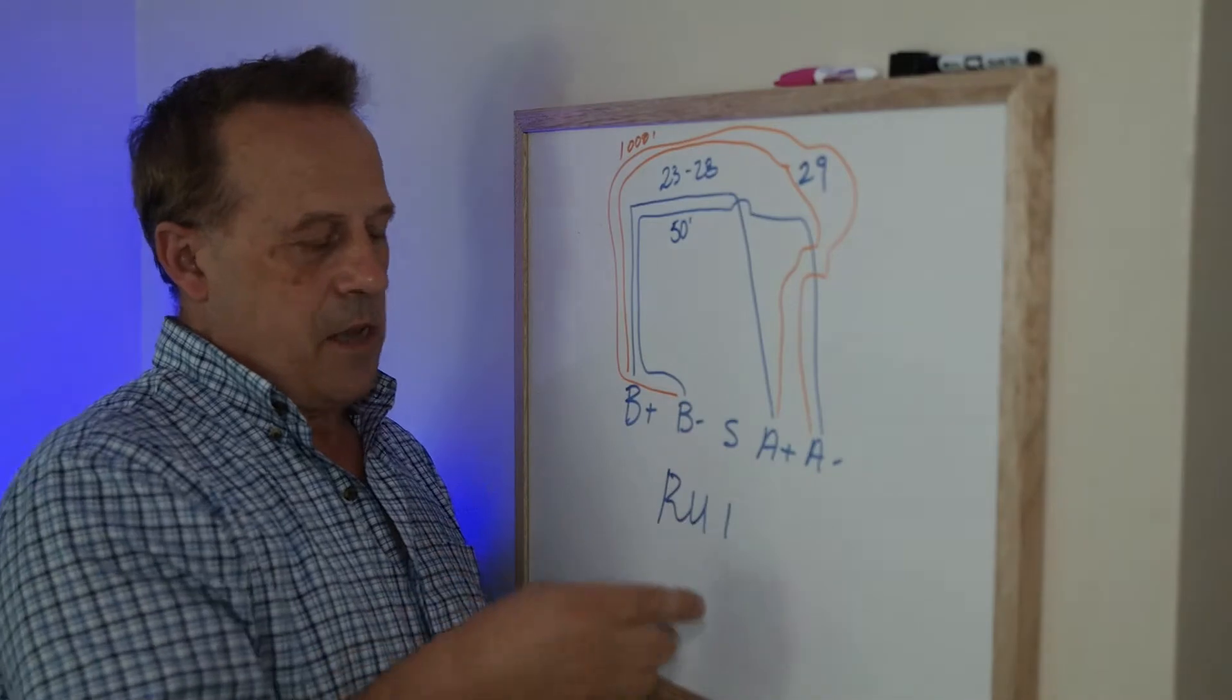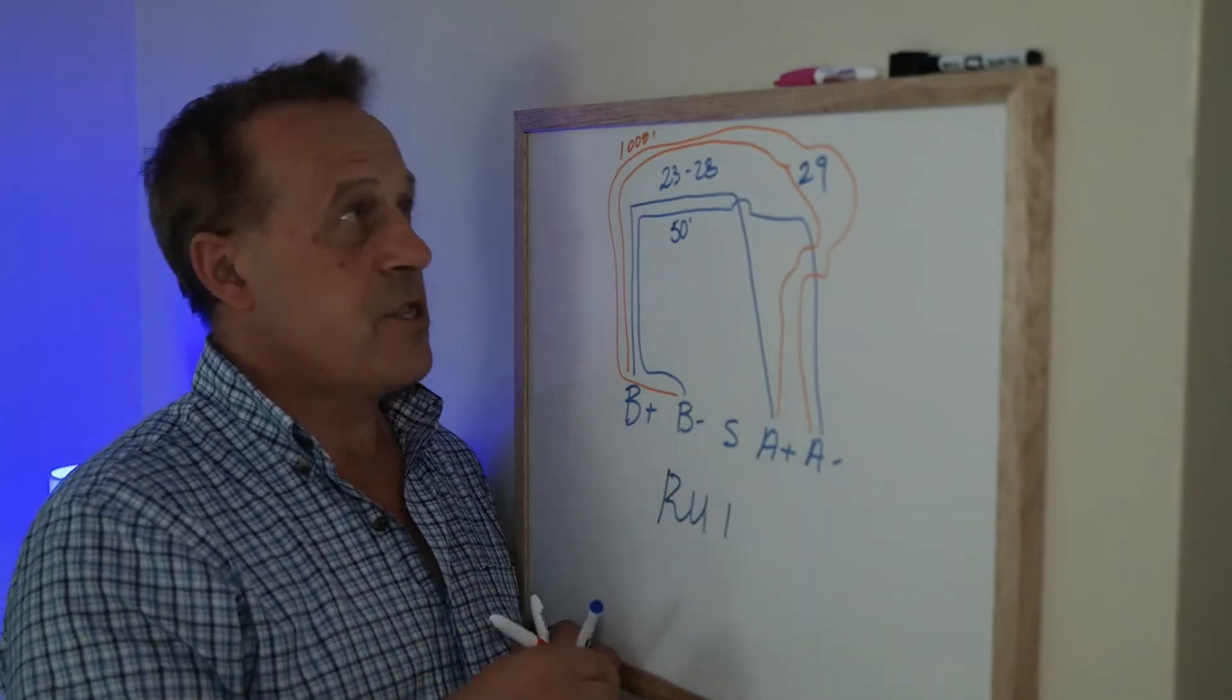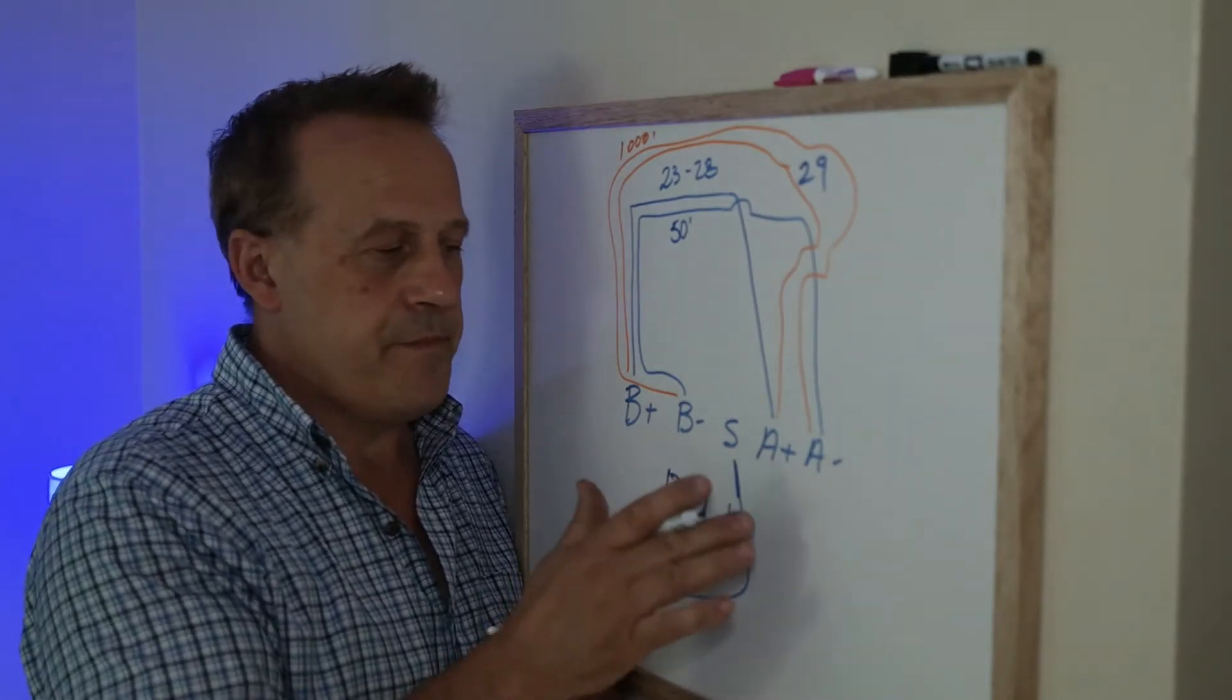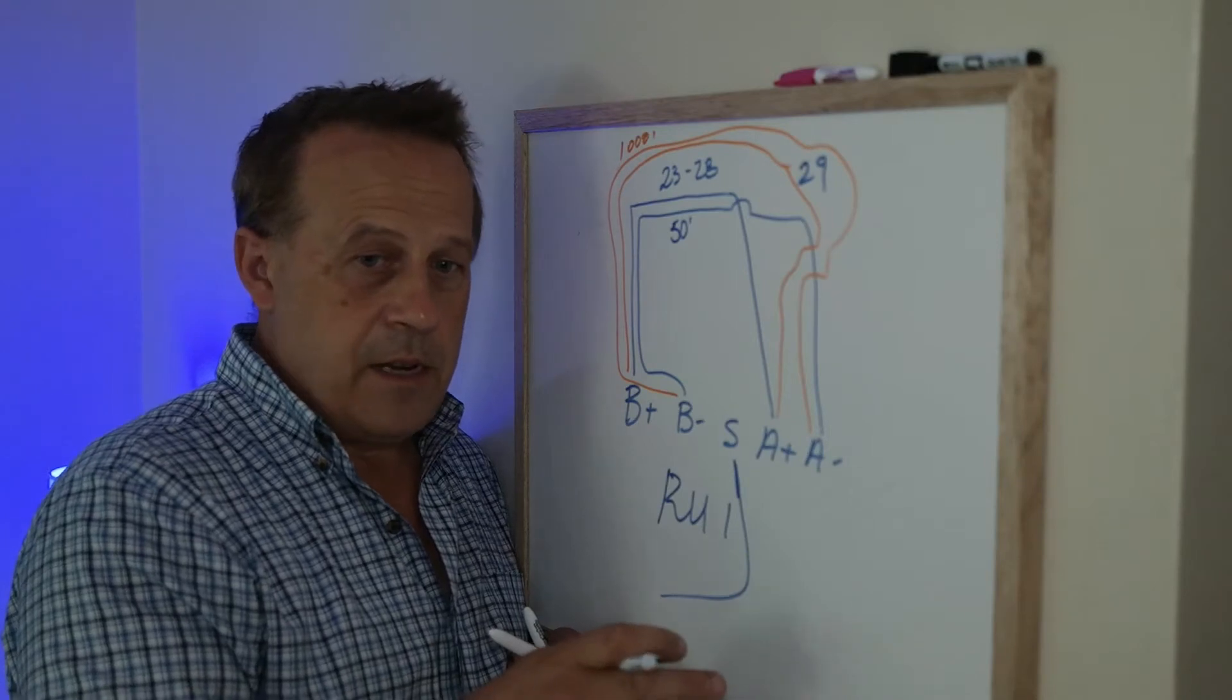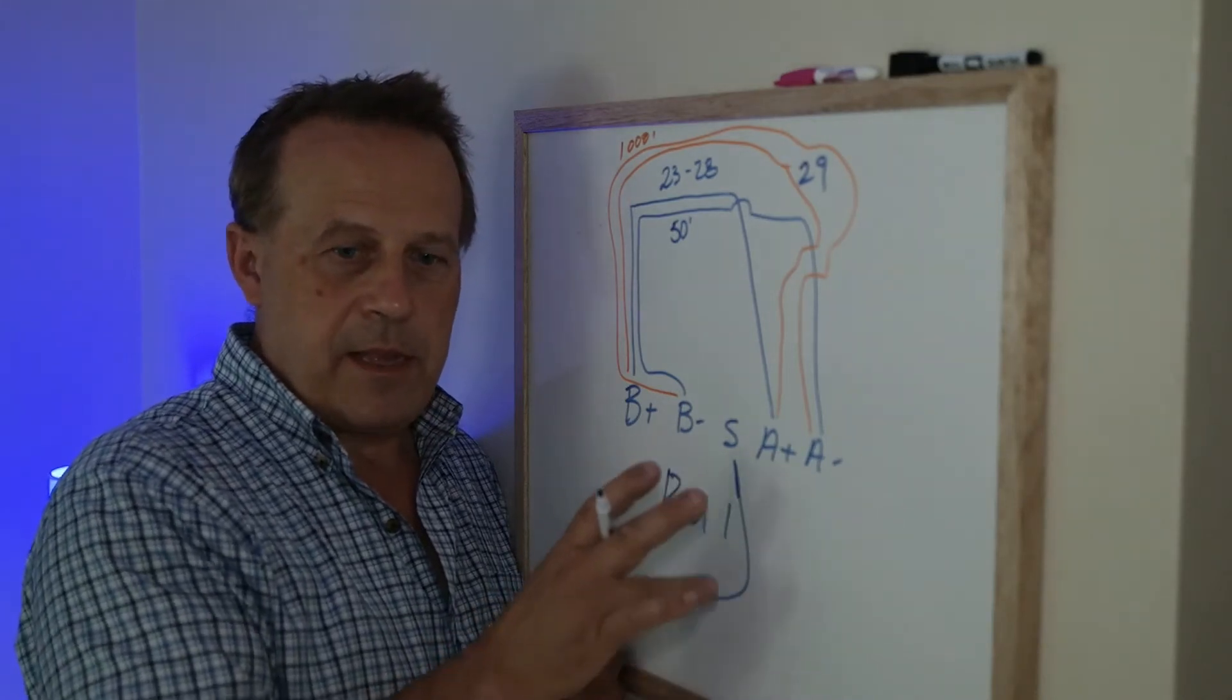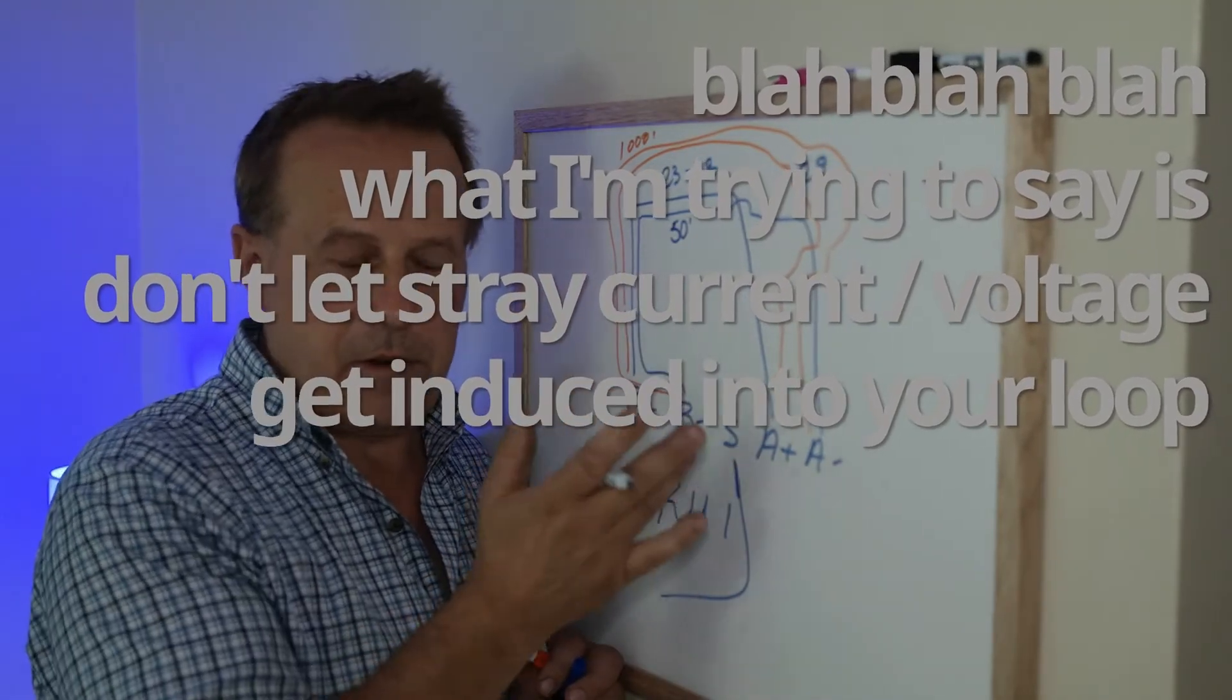So I eliminated this double loop because all of these wires terminated at the panel. It wasn't that difficult to do. And then I added a ferrite bead and I added the shield. Now the shield, I've got a green marker. The shield, you only connect it at one port, one point. One, there's only one termination. And that goes, you don't break it. You continue it and you do not tie it to ground. You do not tie it at both ends. You only tie it at one side. The idea is because you want to avoid ground loops or shield loops. You want to eliminate the possibility that if voltage does get induced into here, you don't want that to have a difference between this shield and say a hundred feet away or a thousand feet away.